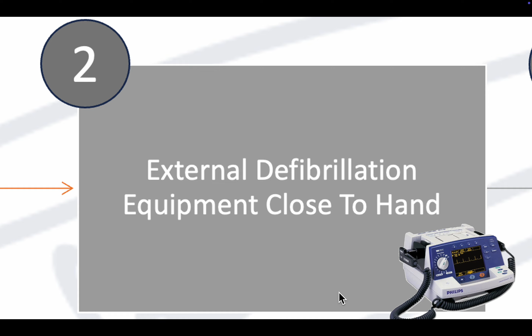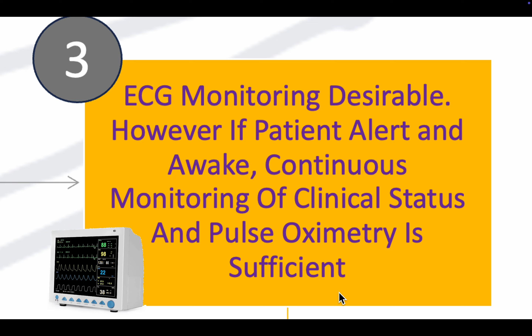It's important that external defibrillator equipment is available close at hand within the theater or theater complex. ECG monitoring is desirable. For anesthesia, that's 100%. But if it is for sedation or in the ward, and the patient is alert and awake, continuous monitoring of clinical signs is fine, and just a pulse oximeter will be enough. A clinical magnet, separate to any other magnet, is provided by the pacemaker companies and should be available for any patient who is pacemaker dependent or has an ICD. And it's great if you have a reprogramming facility available and a cardiorespiratory team available 24/7. That's fantastic.